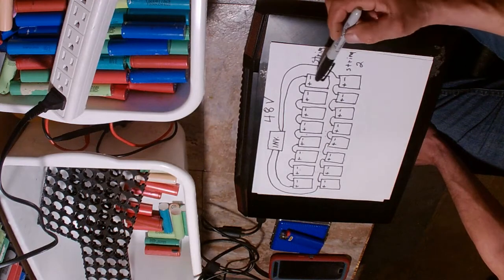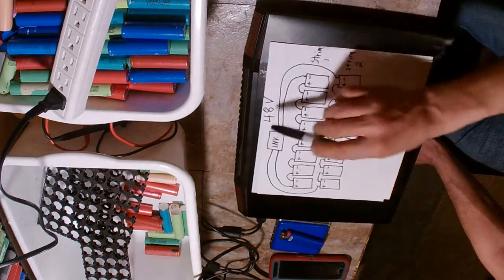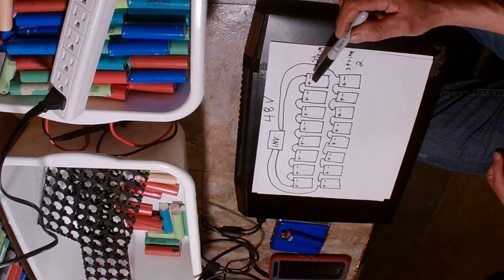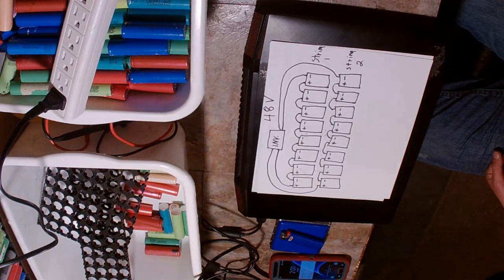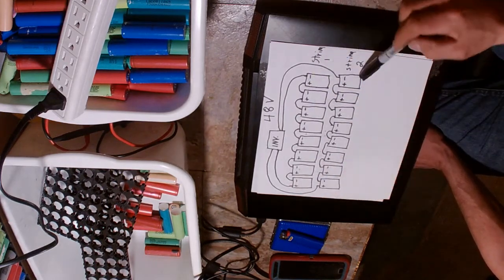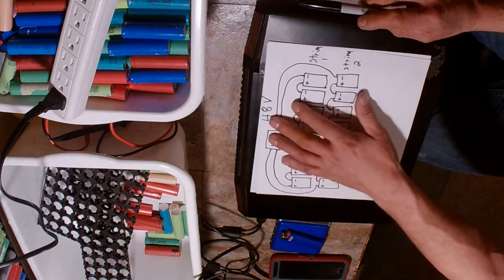In my 48 volt system, the 8-battery string has a connector from battery number 1 to battery number 8 that goes to the inverter. Both strings draw from battery 1 and battery 8. When I've done maintenance and checked water top-ups, battery 8 and battery 1 in both strings absorbed twice as much water as batteries 2 through 7 in between.